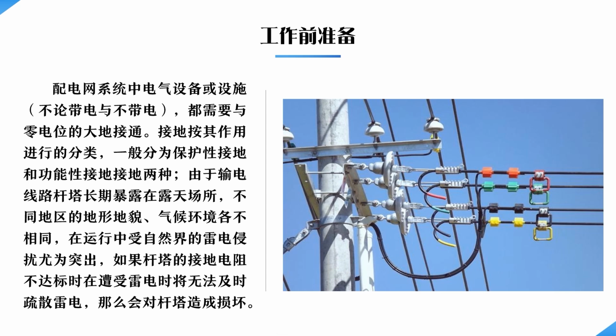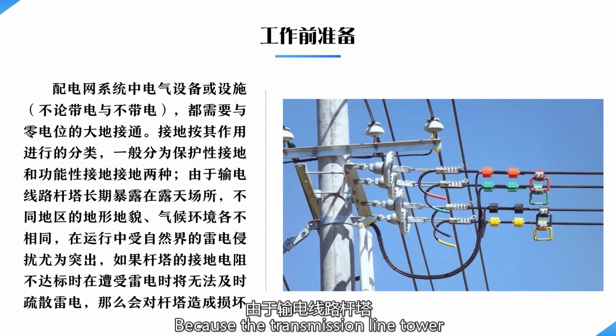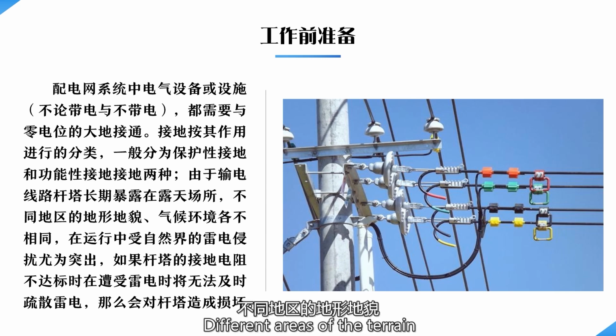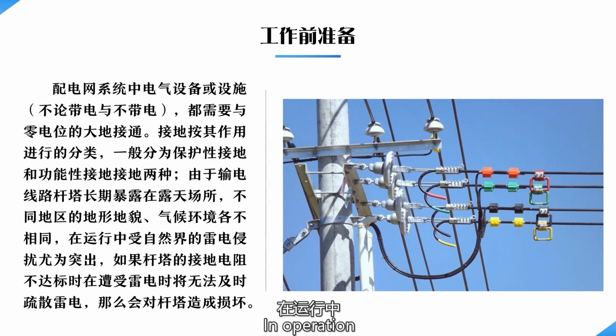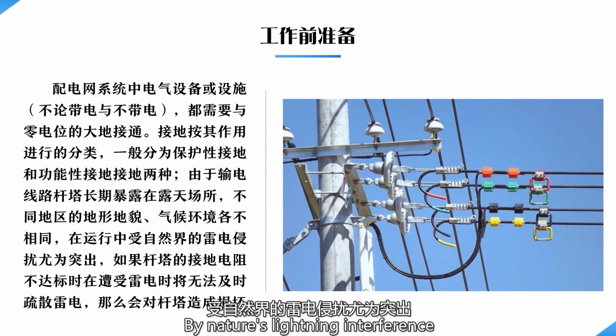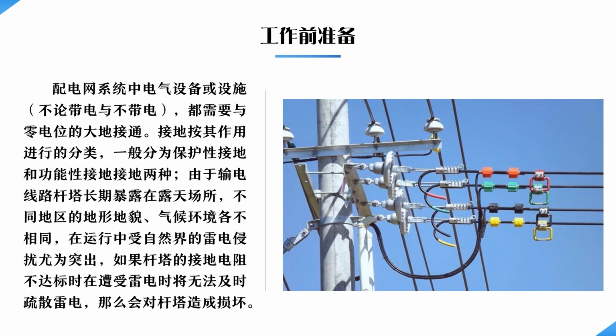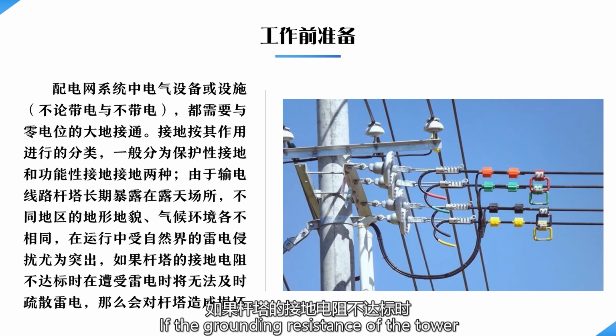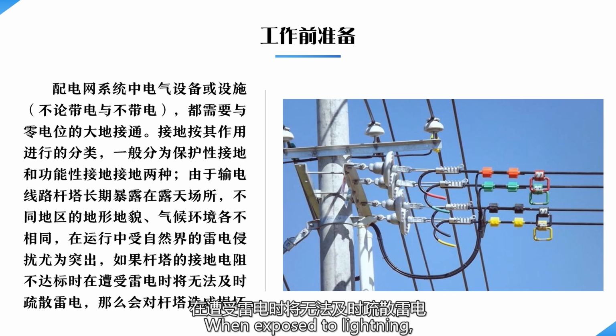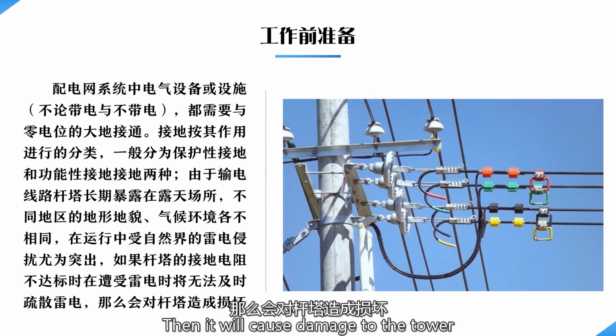Because the transmission line tower is exposed to the open air for a long time, and the terrain and climatic environment vary in different areas, interference from lightning is particularly prominent in operation. If the grounding resistance of the tower is not up to standard, when struck by lightning it will not be able to evacuate the lightning in time, and this will cause damage to the tower.